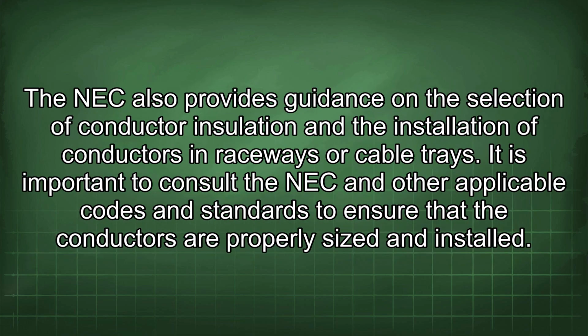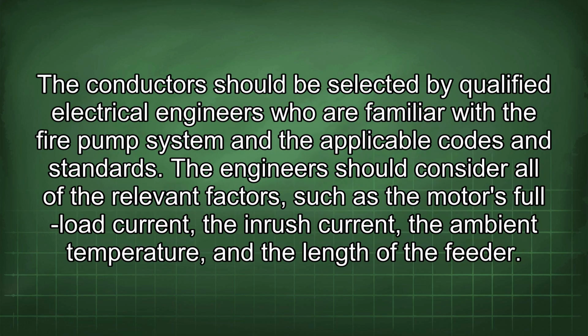The NEC specifies the minimum ampacity of the conductors, as well as the allowable voltage drop. The NEC also provides guidance on the selection of conductor insulation and the installation of conductors in raceways or cable trays. It is important to consult the NEC and other applicable codes and standards to ensure that the conductors are properly sized and installed. The conductors should be selected by qualified electrical engineers who are familiar with the fire pump system and the applicable codes and standards. The engineers should consider all of the relevant factors, such as the motor's full load current, the inrush current, the ambient temperature, and the length of the feeder.